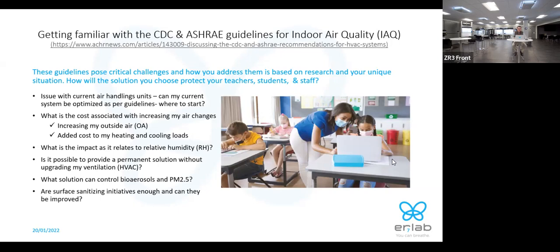One school, actually a middle school and a high school here in Bedford, Massachusetts, did everything the CDC and ASHRAE recommended. They increased their outside air, they increased their air changes. However, because of those increases, they increased their operational cost exponentially. They were spending on average between $13,000 and $15,000 a month in energy. As soon as they made these increases, after spending millions of dollars upgrading their HVAC system, their monthly spend went from about $15,000 a month up to $47,000 a month.